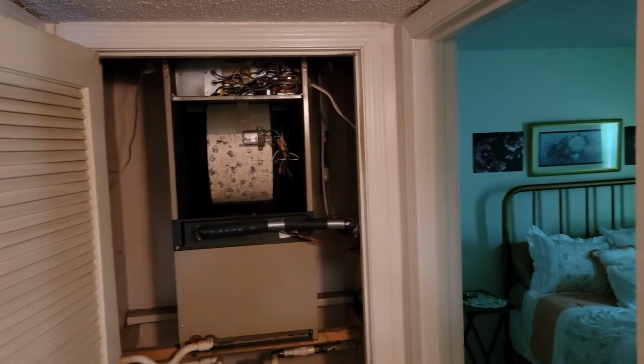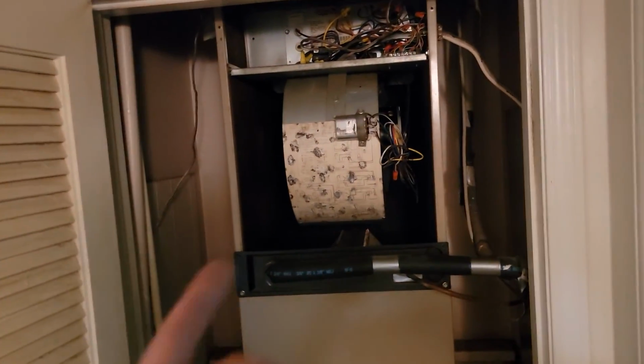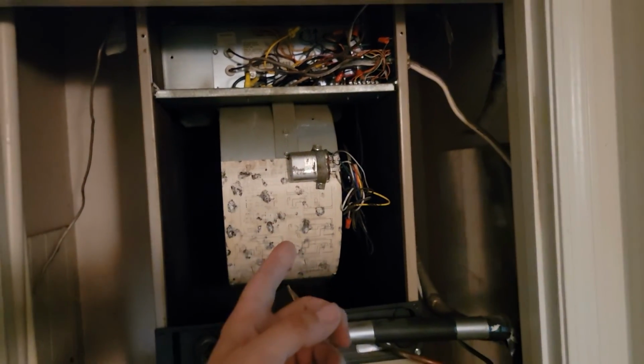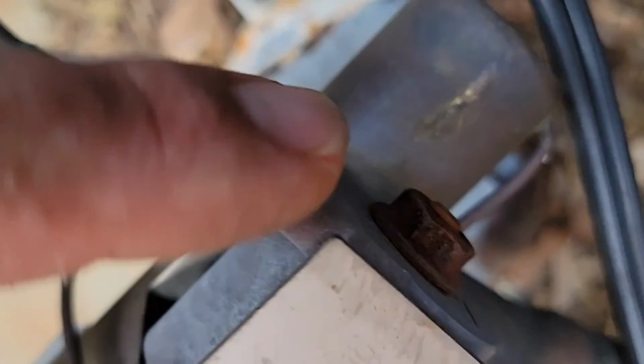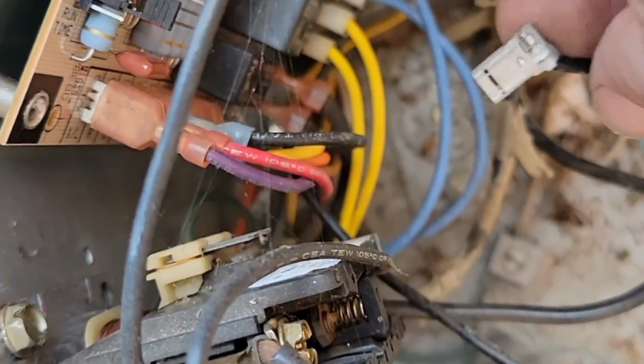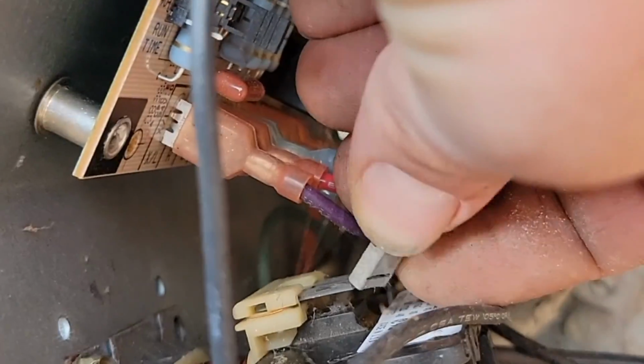Boom. It's the reversing valve coil. All right, I'm gonna unplug the reversing valve coil, plug in my contactor coil, and then we know for sure what the problem is. This right here is the coil that is likely shorted. We're gonna take the wires back off. We are going to take the wire for the contactor coil, which was right here, and put it back on.